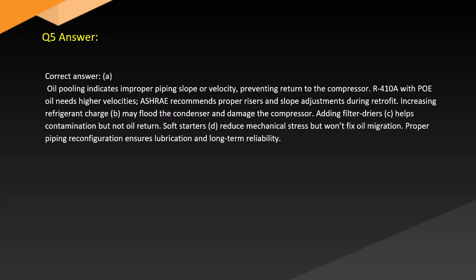Answer. Correct answer: A. Oil pooling indicates improper piping slope or velocity, preventing return to the compressor. R410A with POE needs higher velocities. ASHRAE recommends proper risers and slope adjustments during retrofit. Increasing refrigerant charge (B) may flood the condenser and damage the compressor. Adding filter dryers (C) helps contamination but not oil return. Soft starters (D) reduce mechanical stress but won't fix oil migration. Proper piping reconfiguration ensures lubrication and long-term reliability.